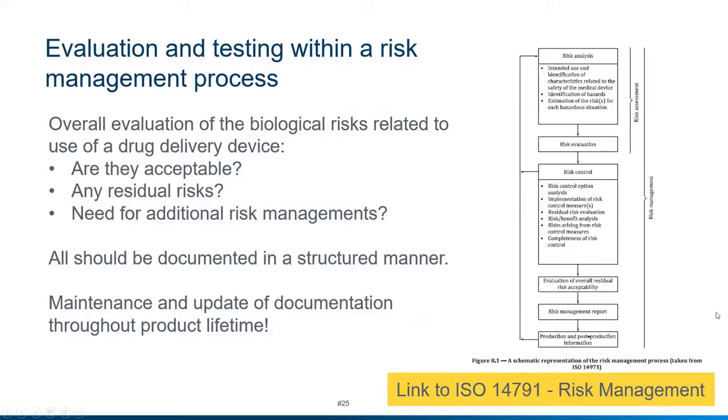So you need to document your risk assessment, and you need to keep it maintained in connection to maintenance of the product documentation. And when you, for instance, have updates to the product design of the device, manufacturing processes, and manufacturing of the device, then you need to also update the biological evaluation.